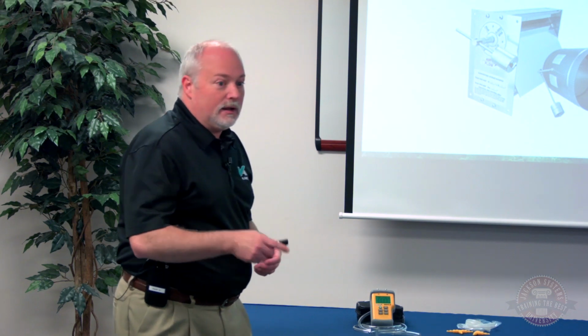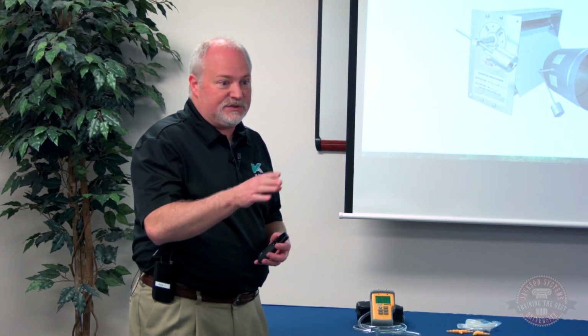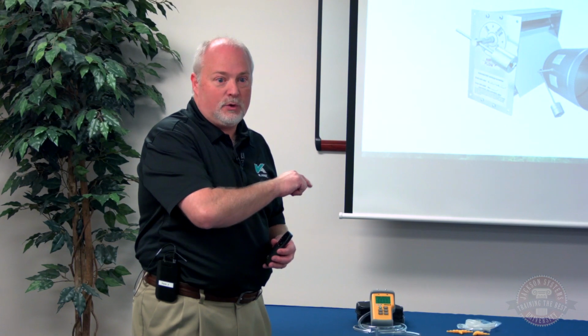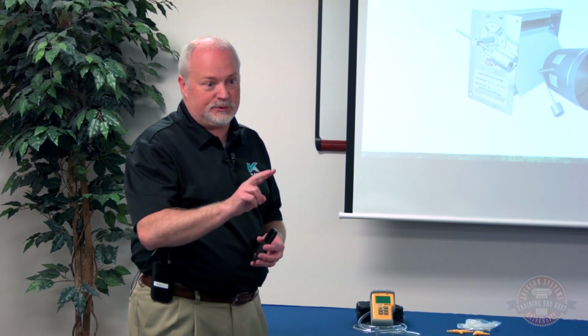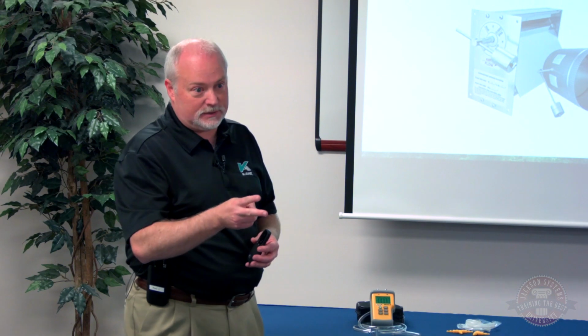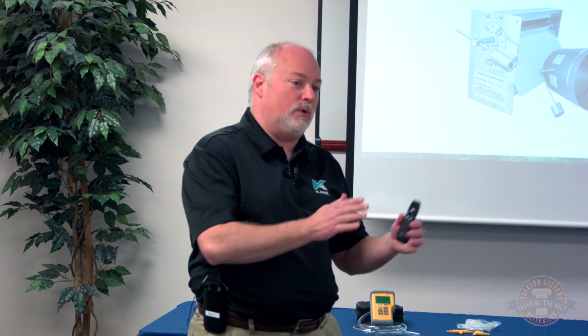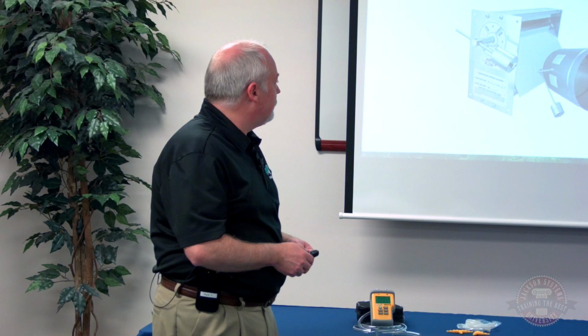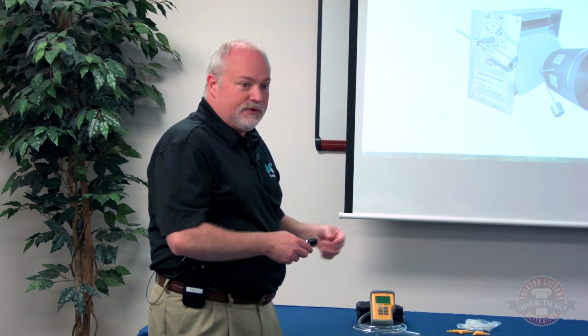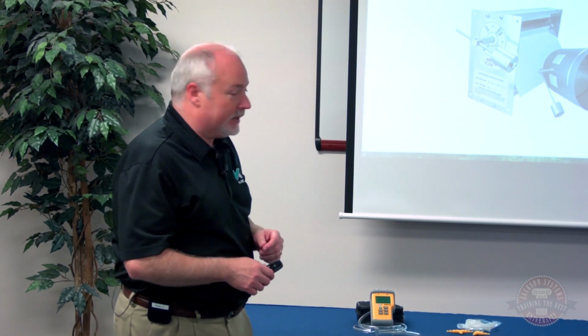And I will mention too, the EM201 reads out to thousands. We do have a 152, which is also a dual input. It only reads to hundreds. So that's a question we get sometimes: what's the difference between the two of those? One reads to hundreds, one reads to thousands. Thanks for the question. Any others on that? But like I say, on the dampers, if you need to set that for air balancing, being able to measure that static pressure so you can make that adjustment to the proper setting if you've got a bypass damper in that system.